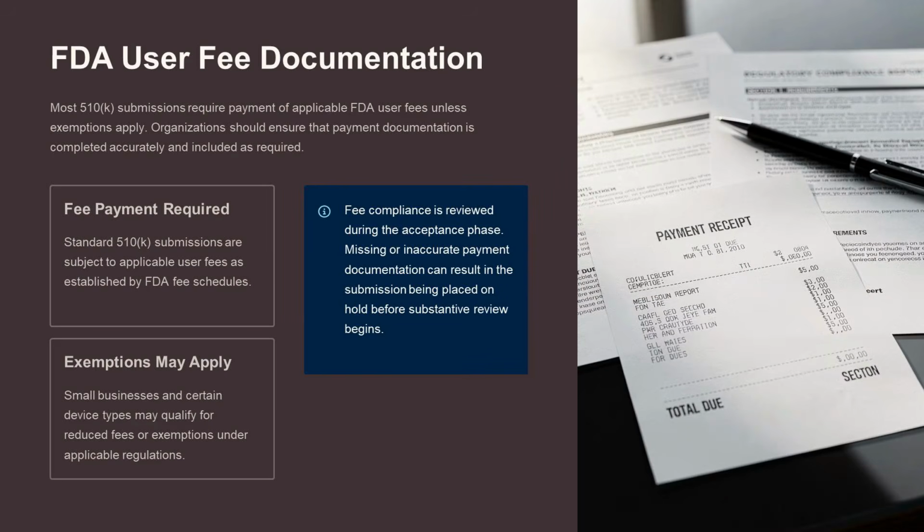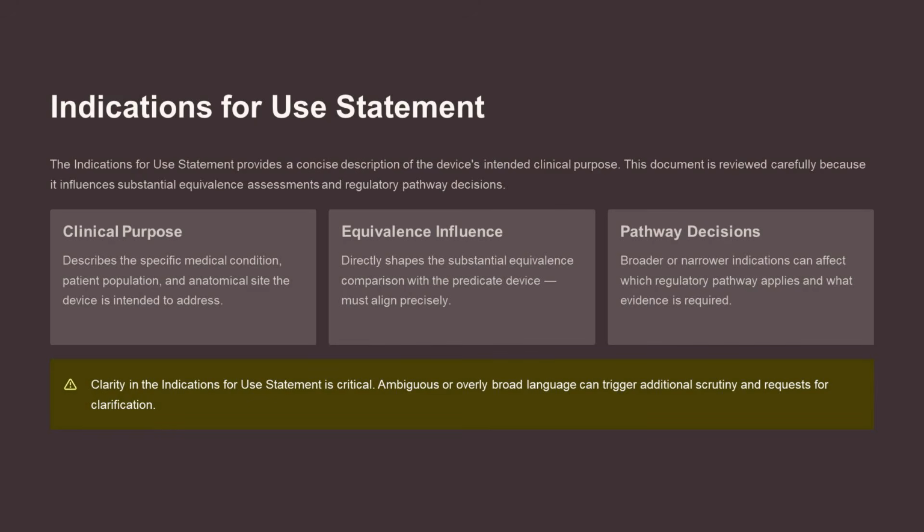Most 510(k) submissions require payment of FDA user fees. Ensure payment documentation is accurate to avoid delays. The indications for use statement describes the device's clinical purpose and is critical for regulatory decisions. Clarity here is essential to avoid additional scrutiny.